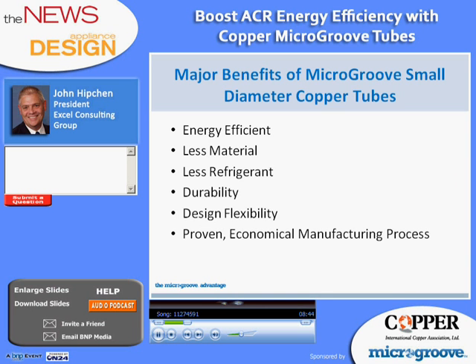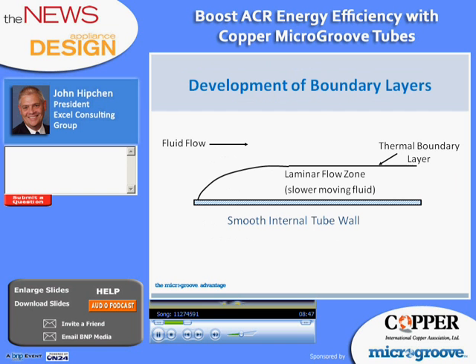So let's turn now toward the technology behind MicroGroove tubes. Take a look at what happens inside a copper tube with respect to boundary layers. Whenever fluid moves through a tube, the fluid closest to the tube wall behaves differently than the fluid in the center of the tube. The fluid next to the tube wall sets up a boundary layer where heat transfer becomes more difficult. And this applies to the hydraulic motion of fluid, as well as the way heat moves from the center of the tube to the tube wall.